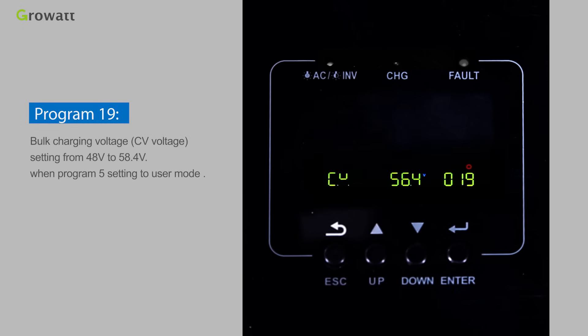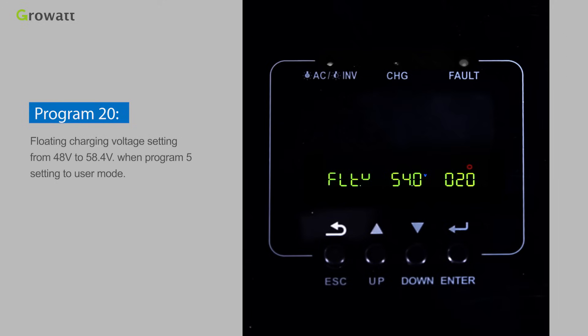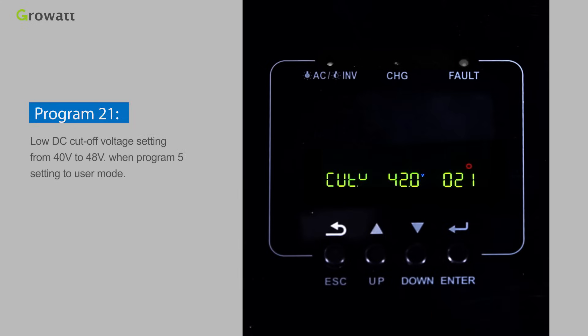Program 19 sets the bulk charging voltage (CV voltage), adjustable from 48 V to 58.4 V, when Program 5 is set to user mode. Program 20 sets the floating charging voltage from 48 V to 58.4 V when Program 5 is set to user mode. Program 21 sets the low DC cutoff voltage from 40 V to 48 V when Program 5 is set to user mode.